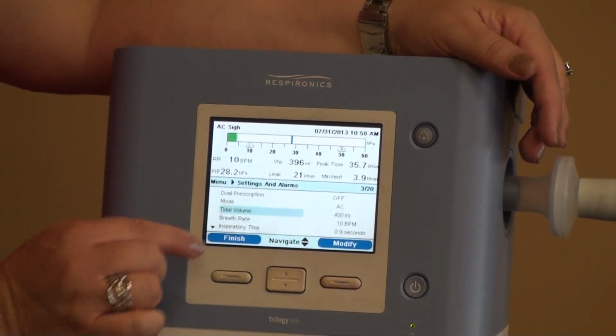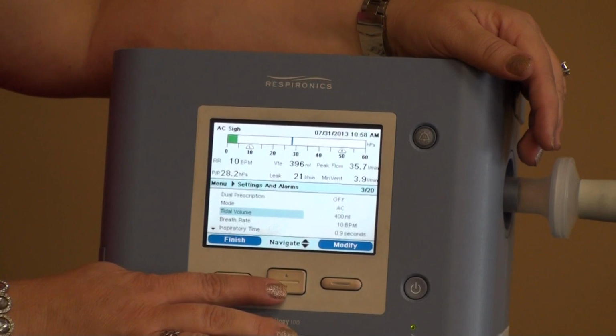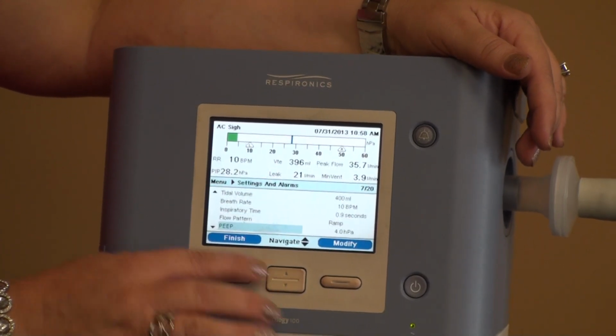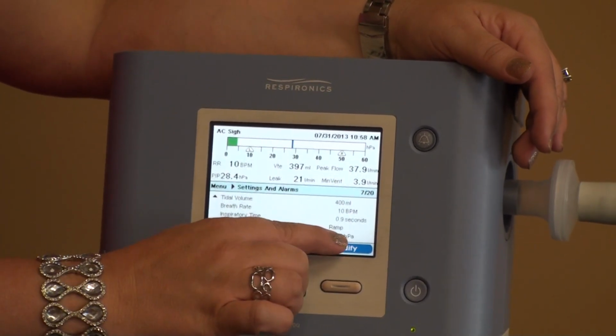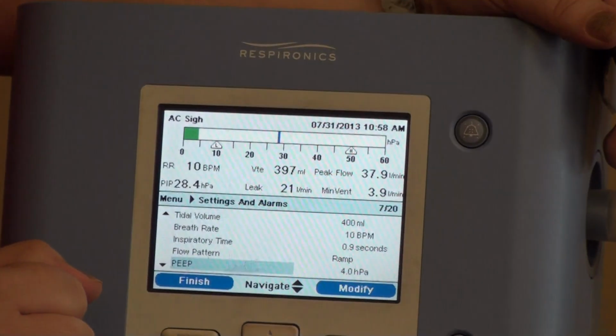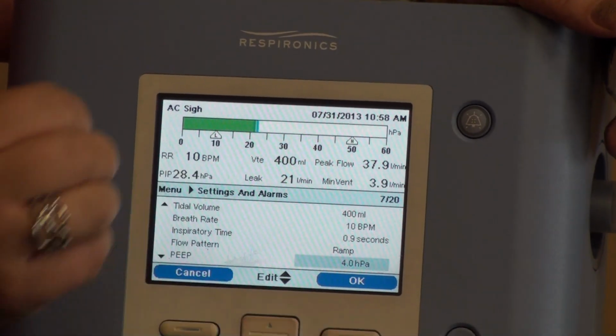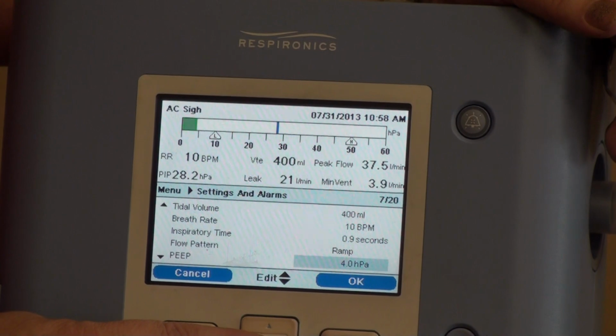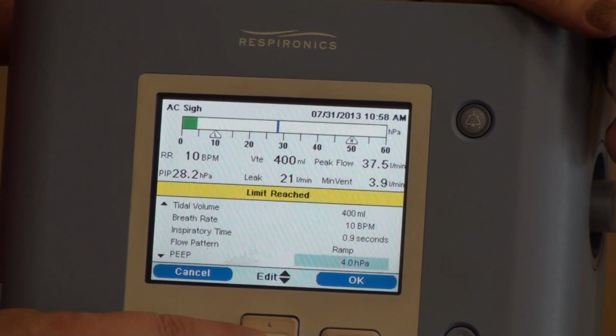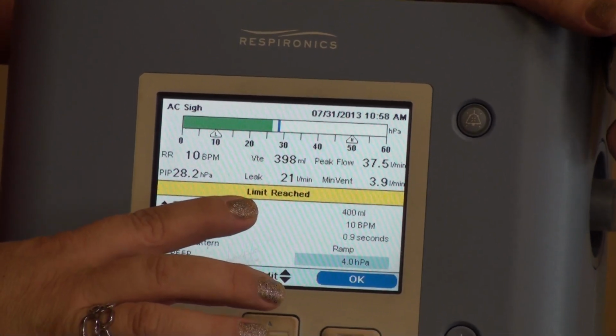Okay, so now I have it on assist control, that's where I want to keep it, so I'm going to press OK. Now say I need to change my PEEP. So I go down until it says PEEP. It says PEEP right here, and it's on 4, but say the physician wanted to go to 3. So I hit modify, and I'm going down, and it won't let me. It's on 4, but it says limit is reached.